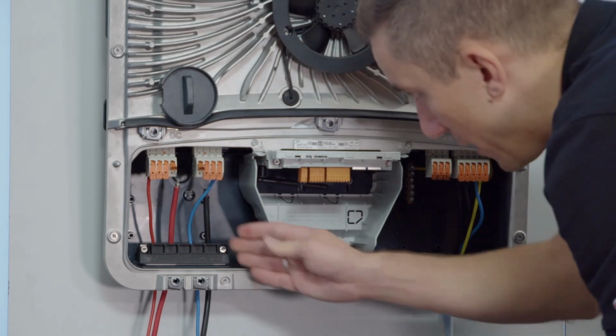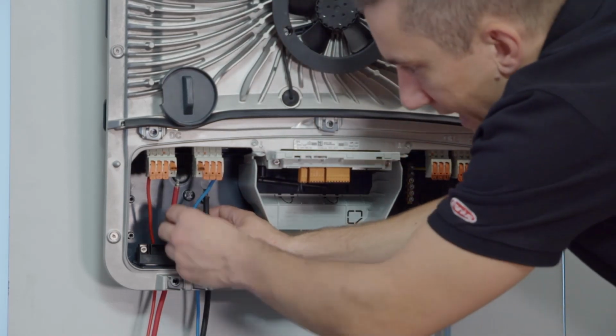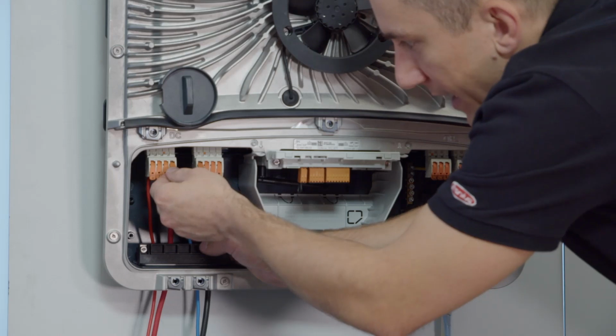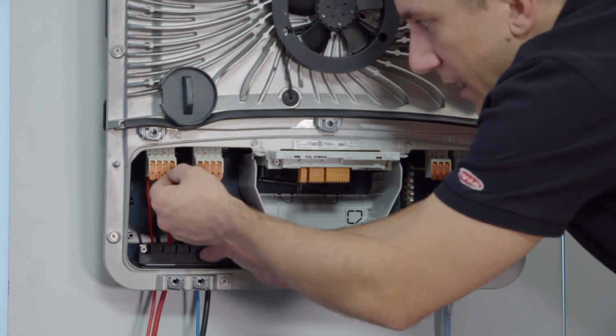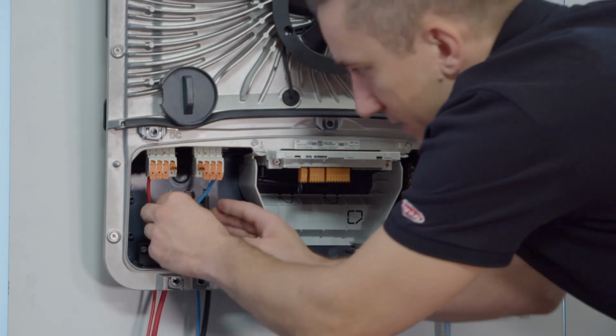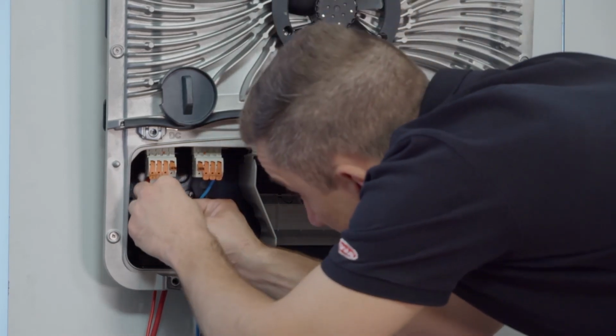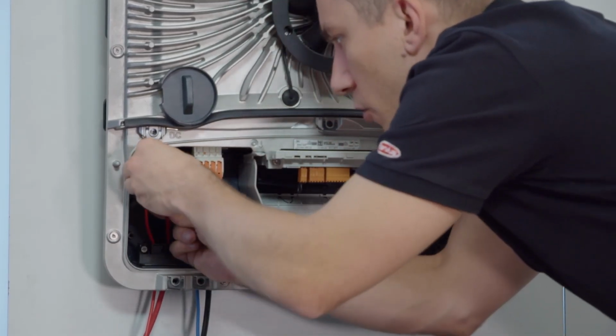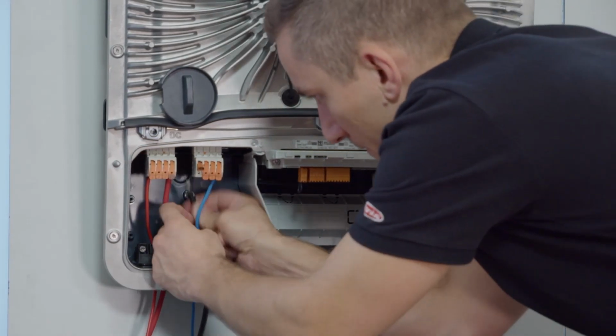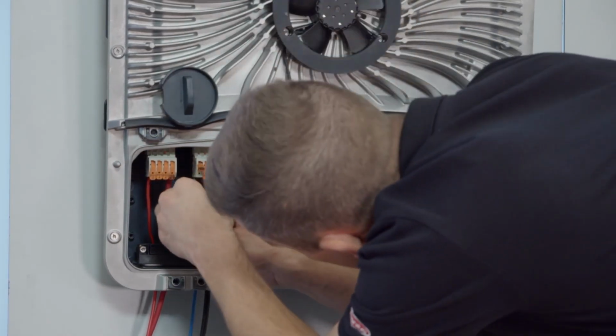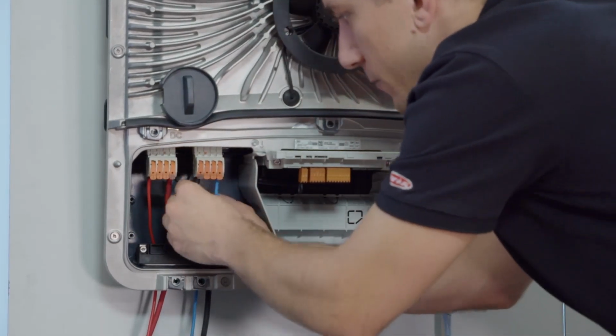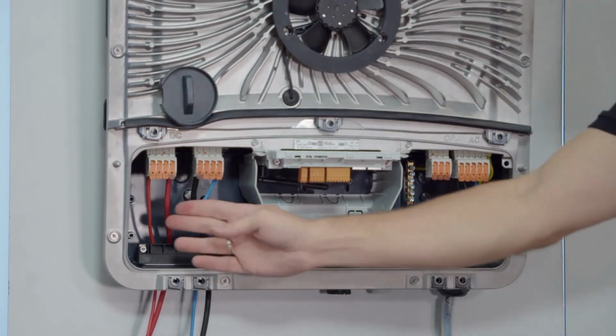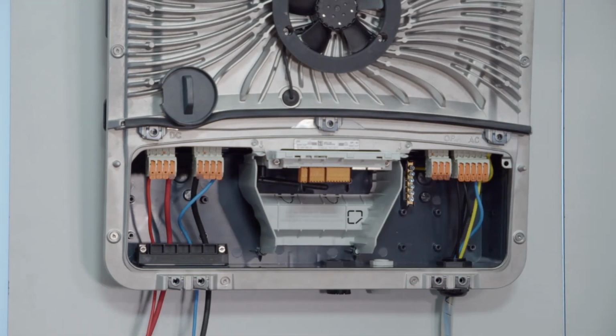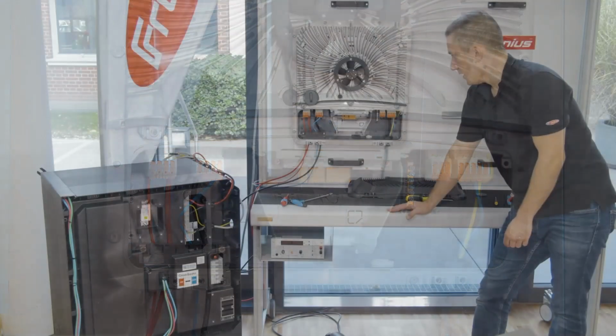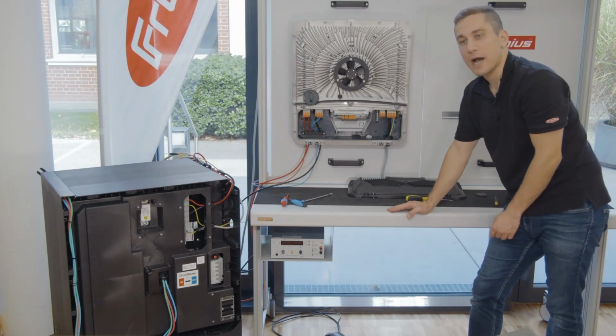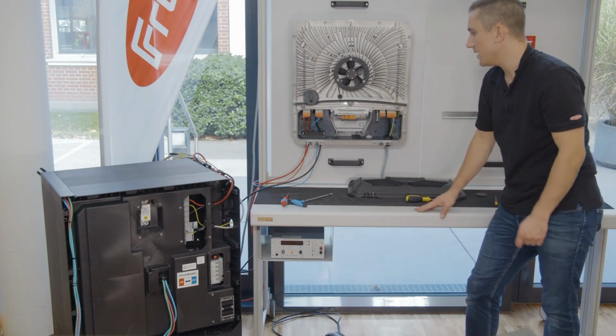So on the DC connection area, all we want to do now is to install the battery cables, and therefore you have 2 specific connection ports. We have here the battery plus and battery minus connection port. And with the DC cables coming from the battery system, we now go into battery plus and into battery minus, and we close our clamps, and therefore the DC connection to the battery system is already finished.